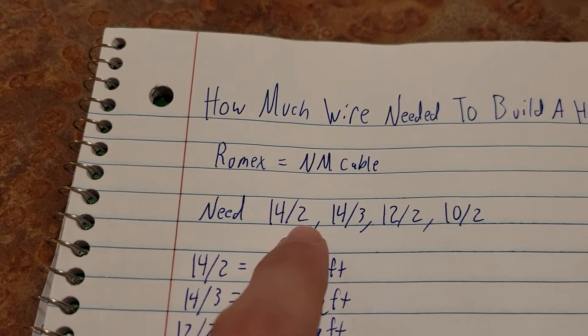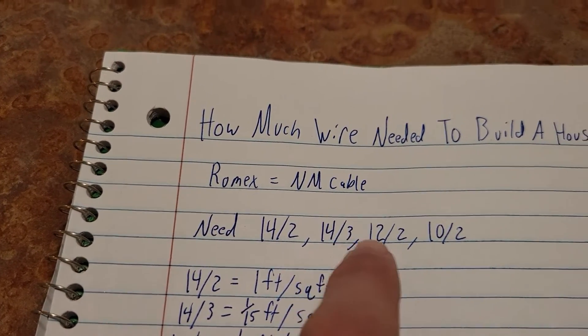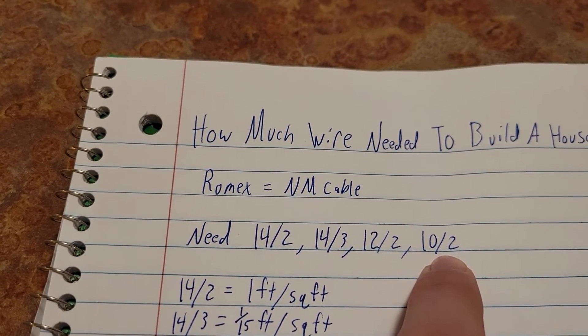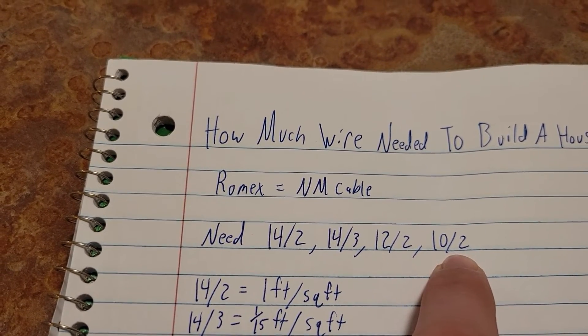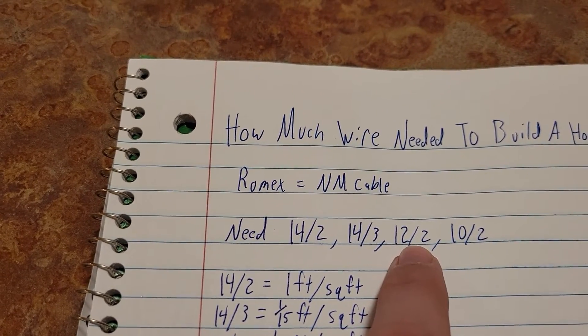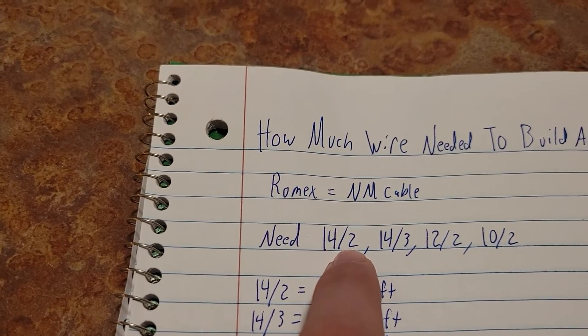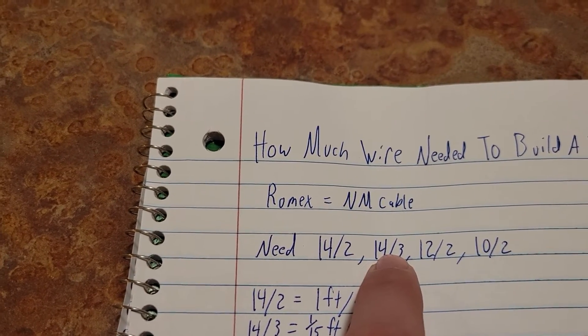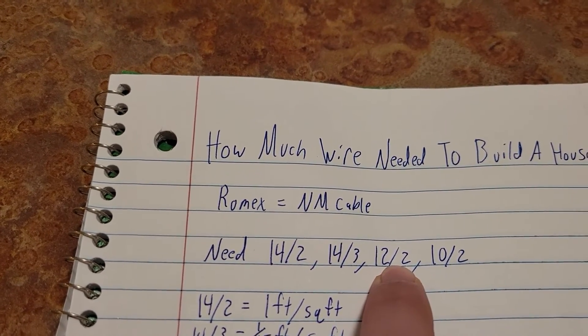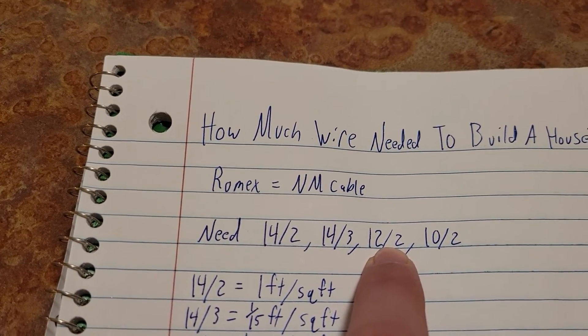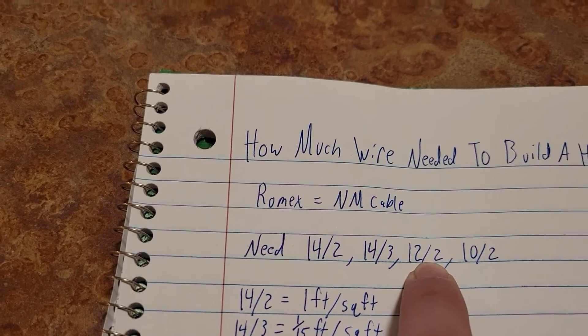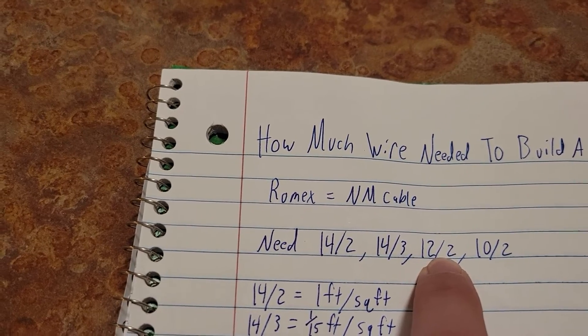Now this is the most cost efficient way that you can wire a house. A lot of contractors have opted to not use 14/2 and 14/3 - they use only 12/2 and 12/3 because it's a larger wire. They feel like they're getting a better heat factor because the larger diameter of the copper doesn't get as hot under the same amount of load.